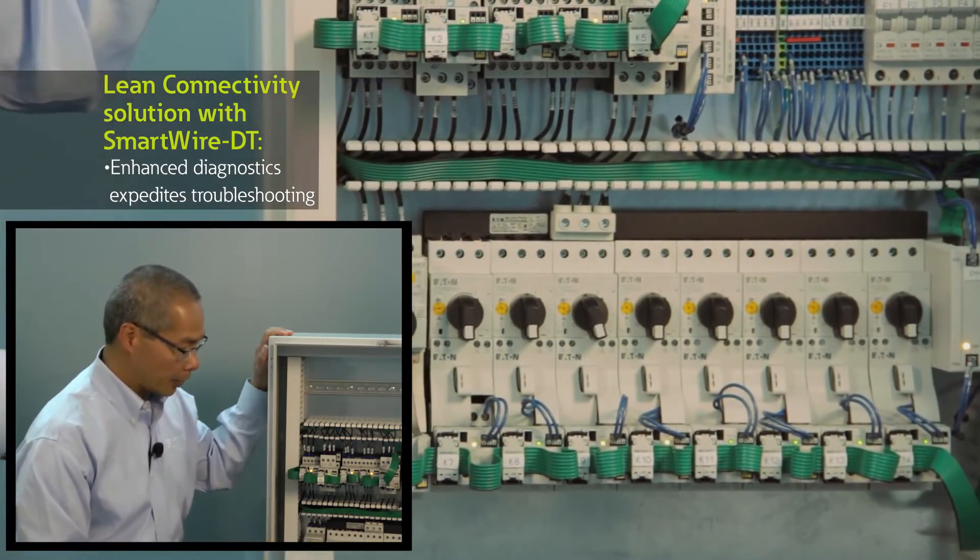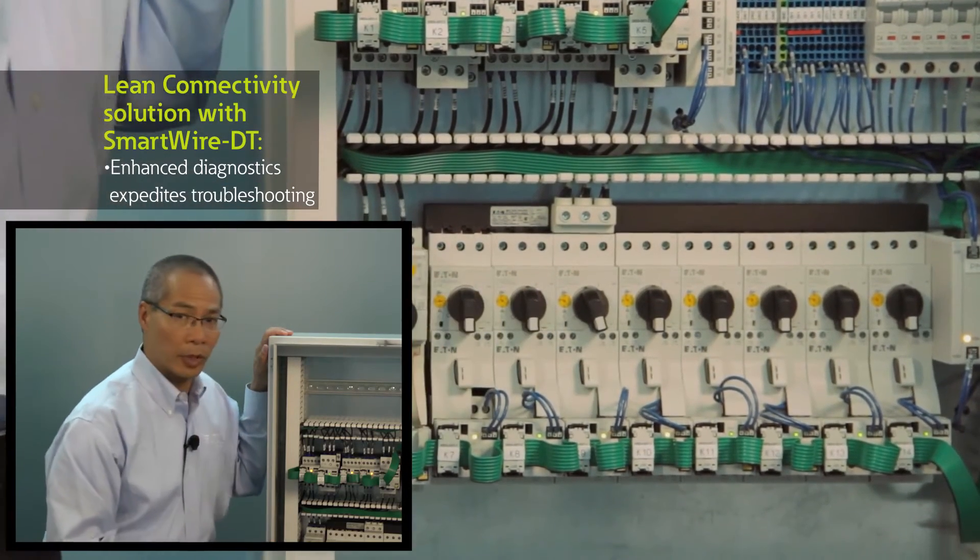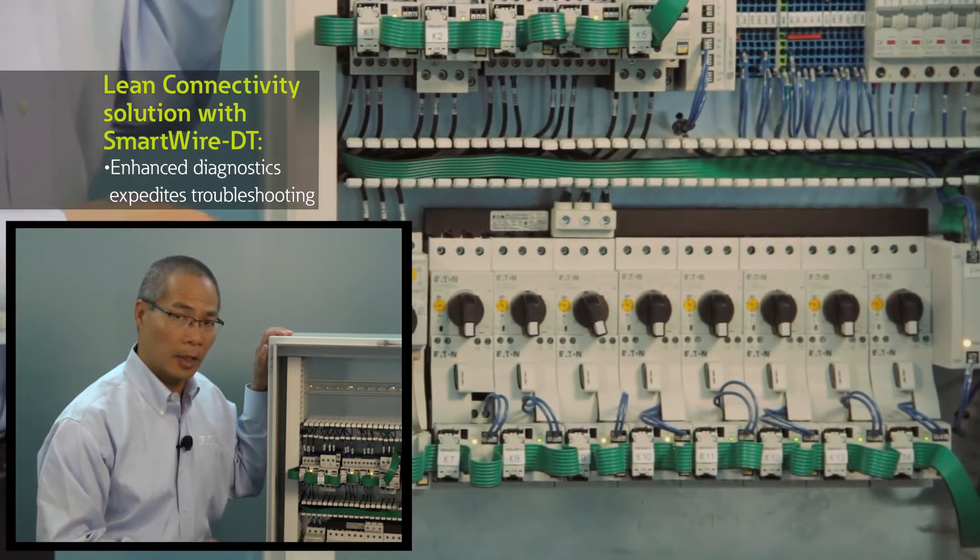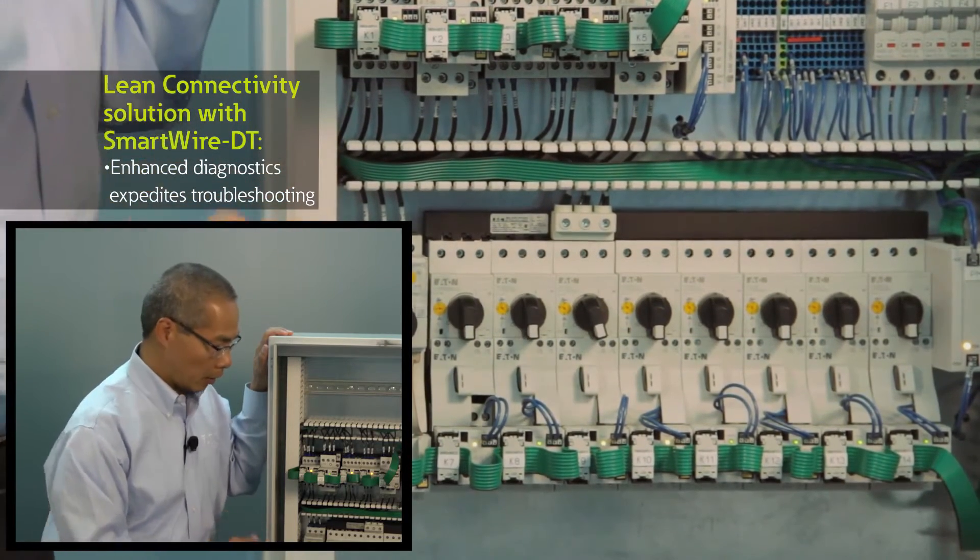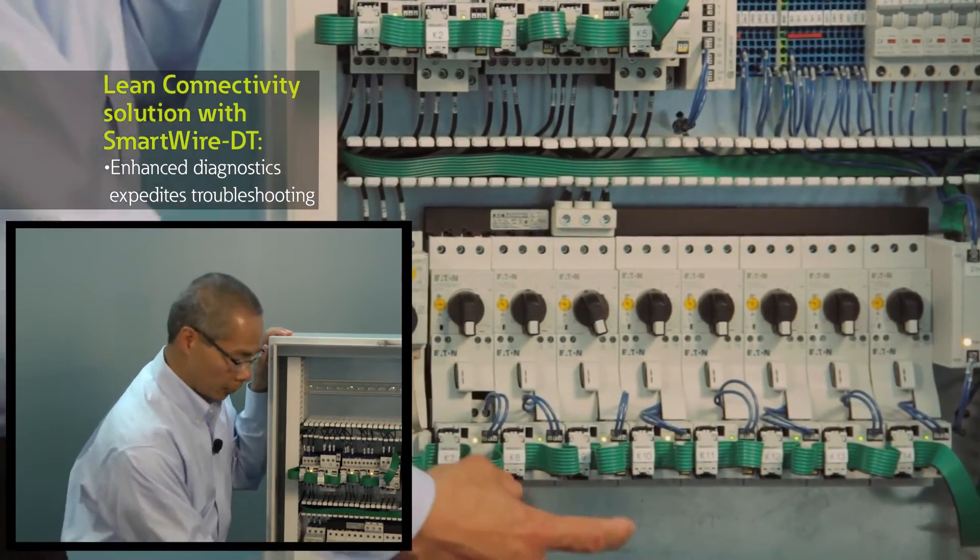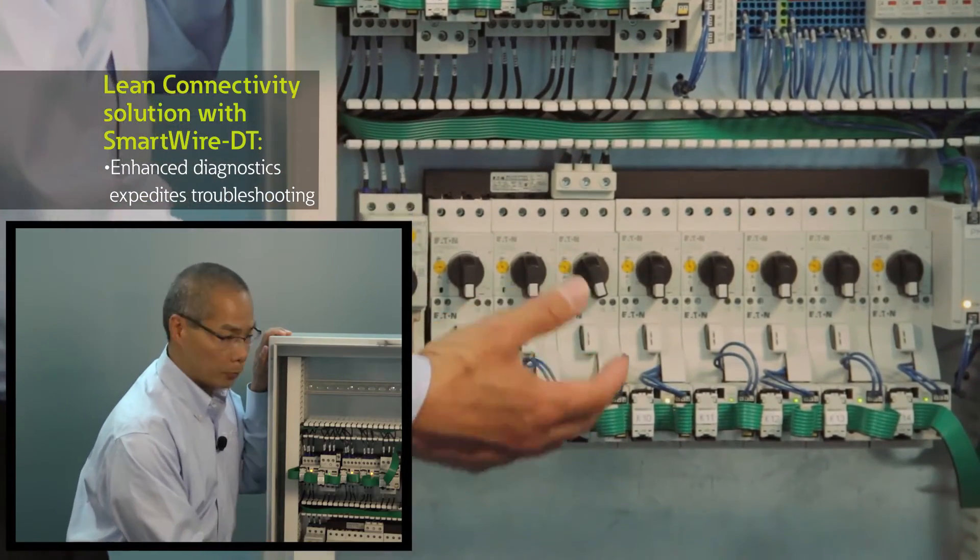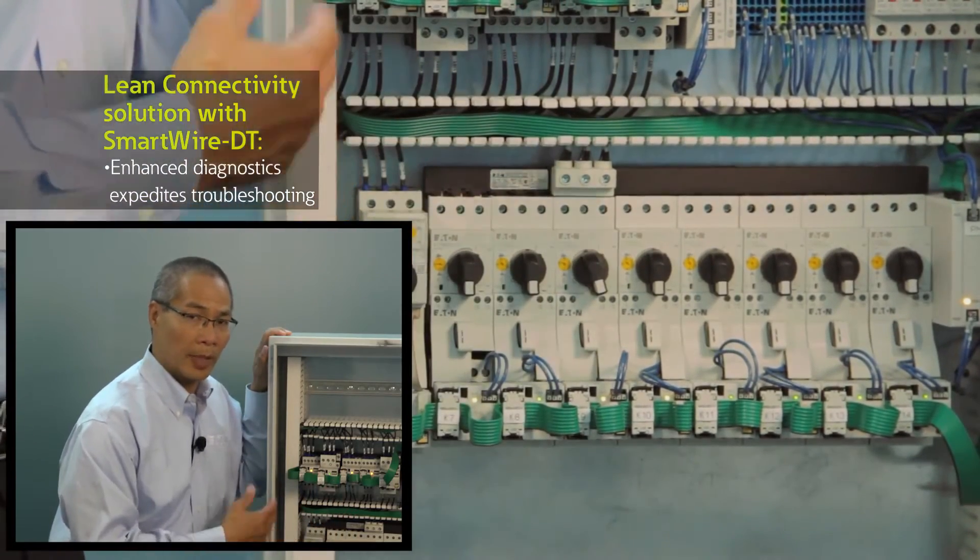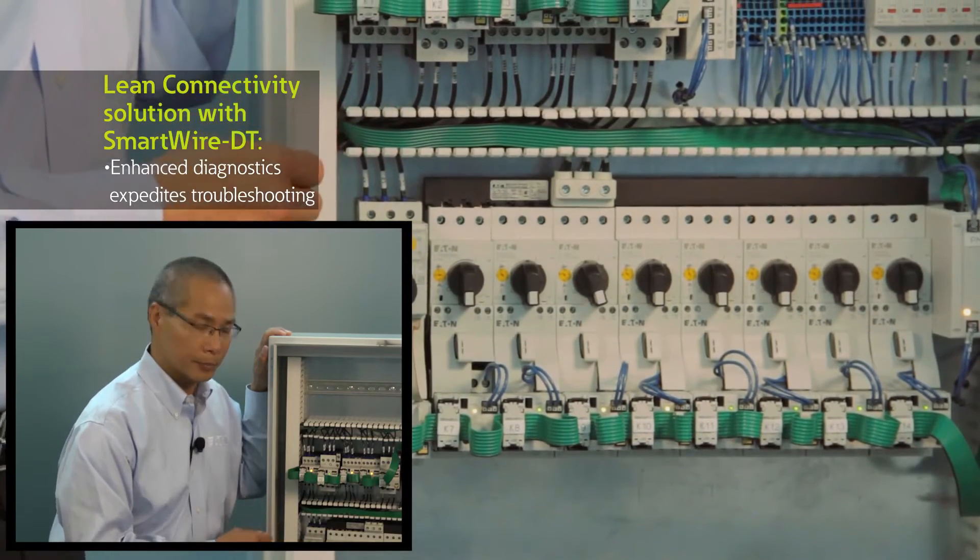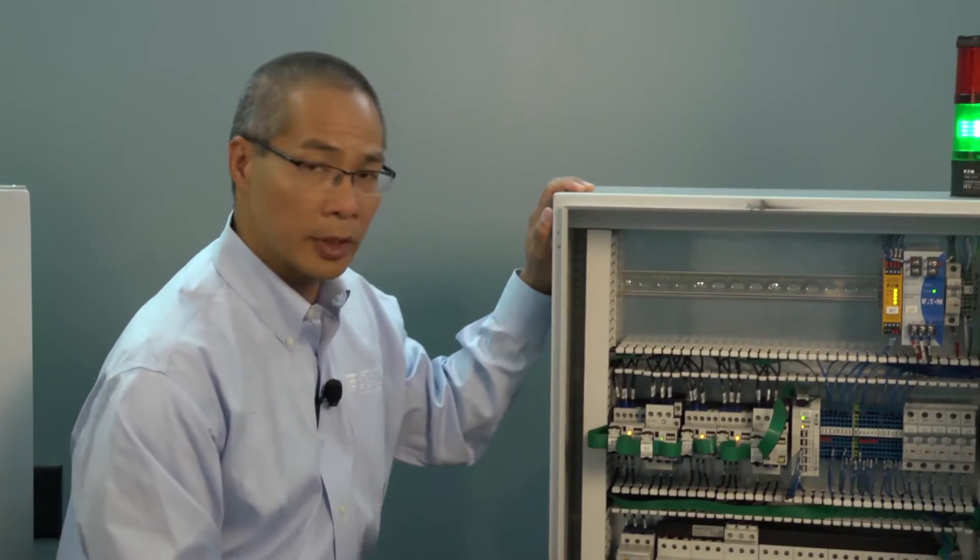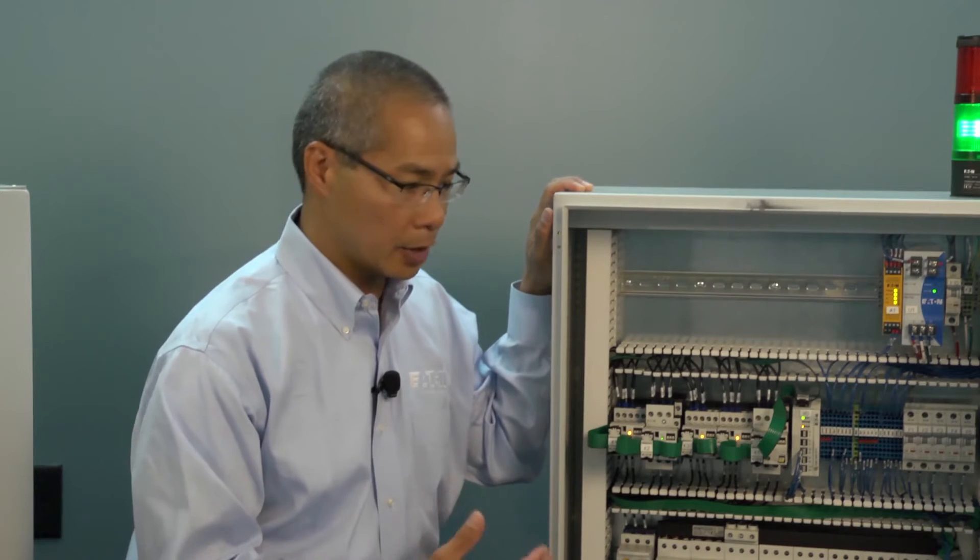If you wanted to compare that with a conventionally wired device, if you wanted to look at the motor load of a standard device, typically you would have to add some sort of current sensor and then wire it back to some analog inputs on the PLC. So this solution can save you time and expense in doing that current monitoring.